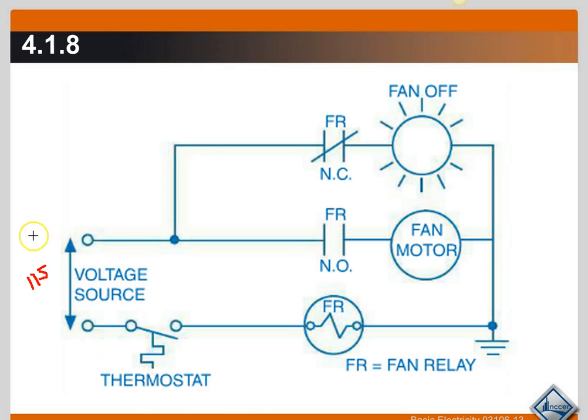So we have 115 volts comes in, comes to the fan relay normally open contact and it cannot pass through because this is open. Comes up here to the fan relay normally closed contact, so that's a straight wire. It powers up the light and the light is on.